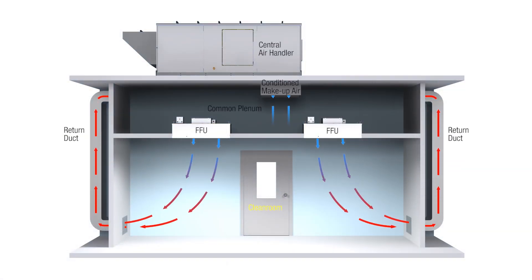A typical clean room system design is to use a negative pressure common plenum, where the FFUs draw surrounding air from the common returns and is mixed with the conditioned makeup air from the air handling unit. One major advantage of a negative pressure common plenum FFU system is that it eliminates the risks of contaminants migrating from the ceiling plenum into the clean space below. This allows for a less expensive and complex ceiling system to be used.